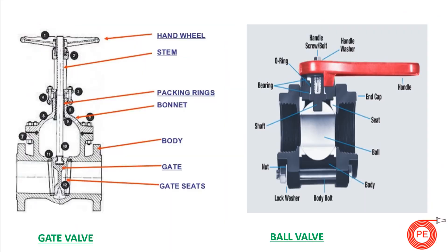Here is a detail of the gate valve parts. The handwheel is the rotating part. Connected to it is the stem, and there are packing rings to prevent the fluid from leaking outside. The bonnet is the main cast body inside which the whole valve system is placed. This is the main body of the valve. The gate — or wedge-shaped material — moves up and down inside the pipe. There are also gate seats to prevent leakage, since metal-to-metal contact is not 100% leak-proof, so seat materials are provided.